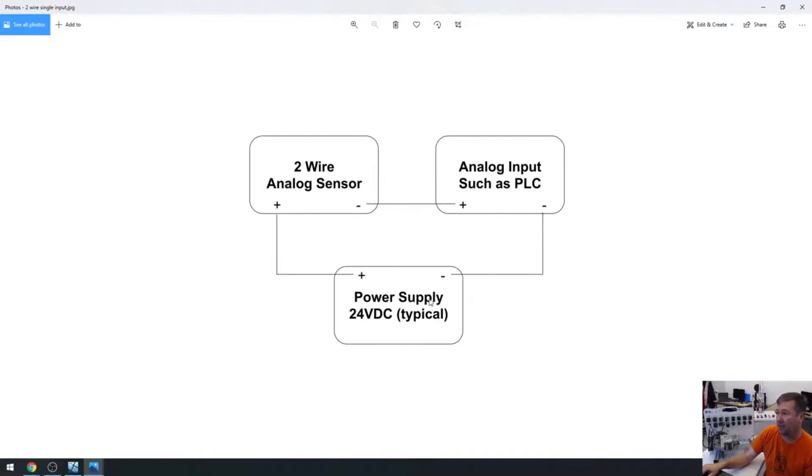And we're going to send 24 volt from our power supply plus to the plus of the sensor. And here's where it gets confusing to people is we're going to take the minus of that sensor and go to the plus or analog input. And then we're going to take the minus or the common and go back to our power supply.